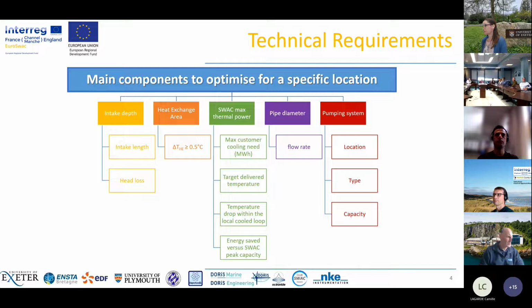Having the thermal power, we can calculate the cooling power, and based on the cooling power, we can calculate the expected flow rate, which is needed to establish or optimize the pipe diameter. It's very important to know the diameter, because flow rate relates to heat exchangers, pumping system, length, etc., and biofouling as well, to prevent biofouling.